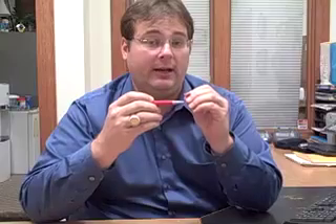The processing part — that's the important difference. That's where sound is actually manipulated by a tiny computer inside the hearing aid. We can manipulate this sound: we can increase the volume, we can decrease the volume, we can do noise reduction where we take out certain noises in the background, and we can fine tune each individual frequency, just like an equalizer on a stereo.